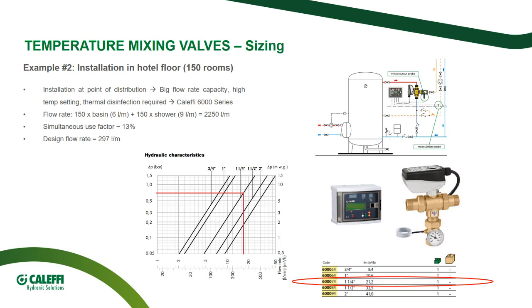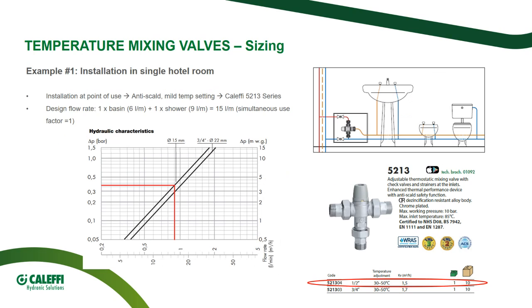Okay, great. Next one. What is the price difference between the thermostatic and the digital versions? Basically it is the regulating element. The thermostatic devices, I don't have any cross-section in my presentation, but inside of them, the thermostatic mixing valve has a wax sensor and an obturator that expands or gets smaller according to the temperature variation. This change in volume will determine the bigger opening or closing of the hot water and cold water inlet.